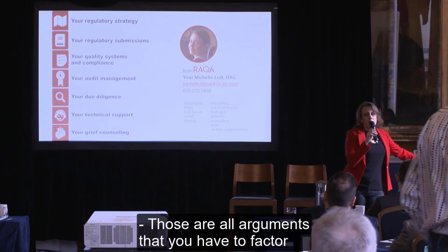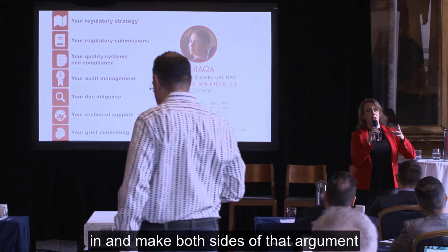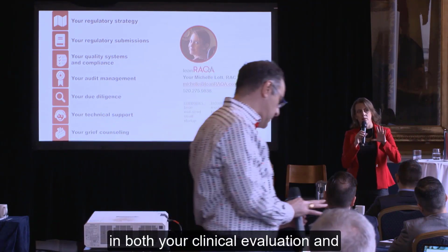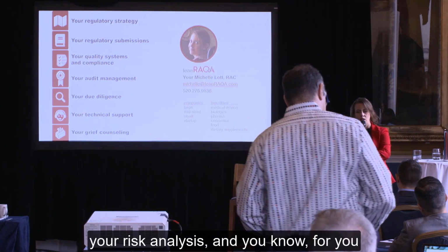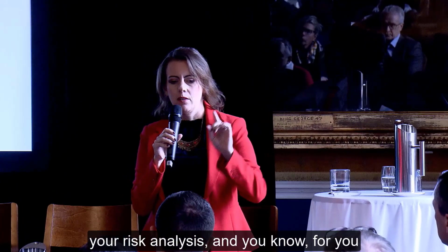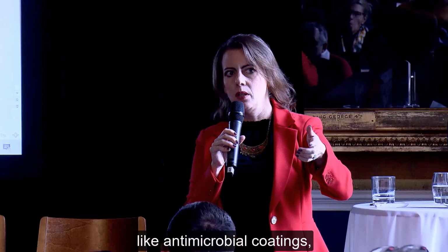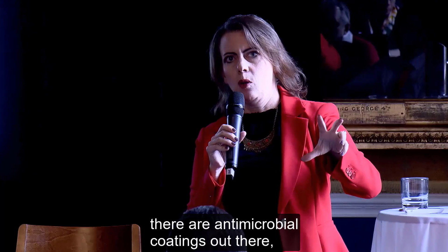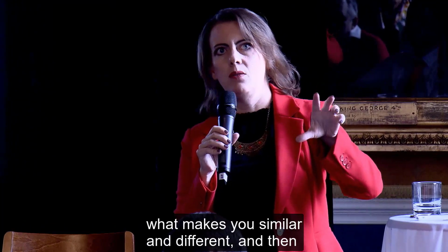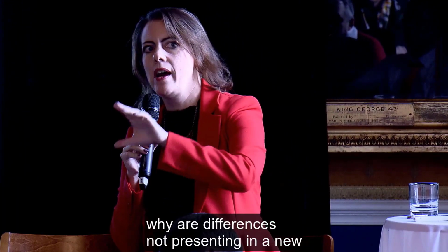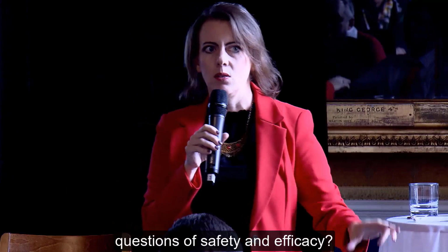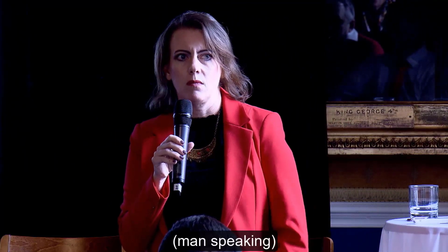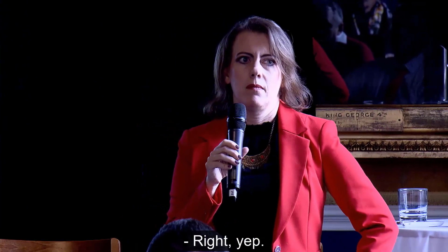Those are all arguments that you have to factor in and make both sides of that argument in both your clinical evaluation and your risk analysis. And for you, like antimicrobial coatings, there are antimicrobial coatings out there. What makes you similar and different? And then why are your differences not presenting any new questions of safety and efficacy? That's my state of the art. Right.